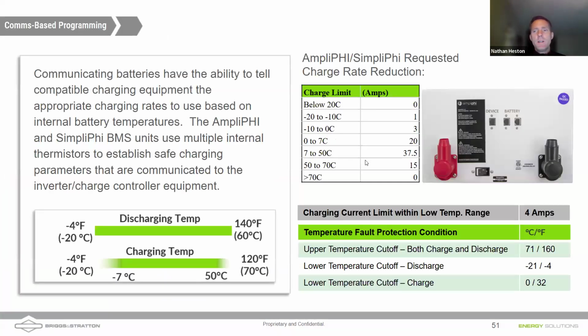So we see those. There are some advantages to our SimpliPHI batteries as well. So one, we can integrate heaters, but we also have a clever way of using the batteries to generate heat. The viscosity of the electrolyte goes up and the internal resistance of batteries goes up at low temperatures. So there's less mobility for the ions as they're migrating through the electrolyte, and that results in the generation of more heat.